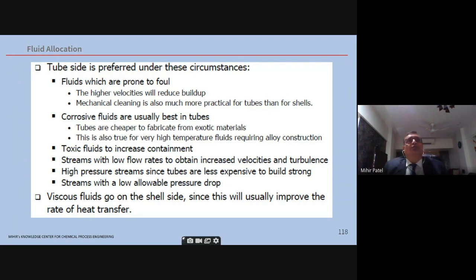Streams with low flow rates to obtain increased velocities and turbulence. High pressure streams. Then tubes are less expensive to build strong as compared to shell side, where very high pressure on shell side, it becomes difficult, costly exchanger. And streams which have a low allowable pressure drop. Viscous fluids normally go to shell side. So this is a fluid allocation thumb rule.